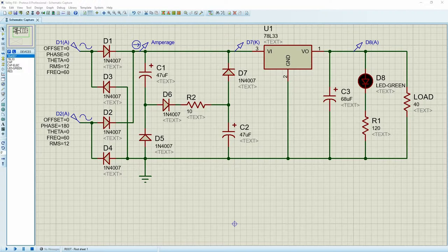And so the answer to this was to add fairly large capacitors onto the motors to compensate for this reactive inductance. So now we have LEDs everywhere. We have the opposite problem. The easiest way to create a DC circuit is with a rectifier and a big capacitor on there. But if you imagine that every light out there has a whack of capacitors on it, then we end up with this capacitive reactance problem. And so they've had for quite some time a standard around power factor correction, or PFC. And your LEDs now have to fall within this PCF specification.